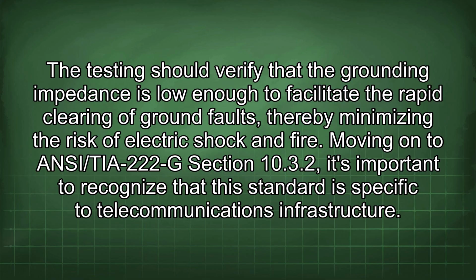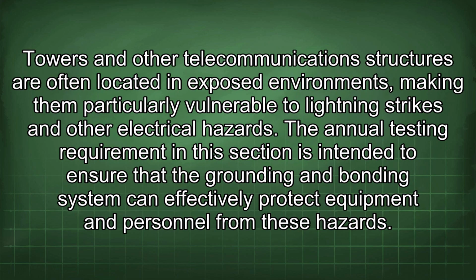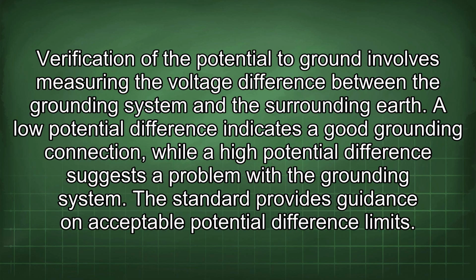Moving on to ANSI/TIA-222-G Section 10.3.2, it's important to recognize that this standard is specific to telecommunications infrastructure. Towers and other telecommunications structures are often located in exposed environments, making them particularly vulnerable to lightning strikes and other electrical hazards. The annual testing requirement in this section is intended to ensure that the grounding and bonding system can effectively protect equipment and personnel from these hazards. Verification of the potential to ground involves measuring the voltage difference between the grounding system and the surrounding earth. A low potential difference indicates a good grounding connection, while a high potential difference suggests a problem with the grounding system. The standard provides guidance on acceptable potential difference limits.